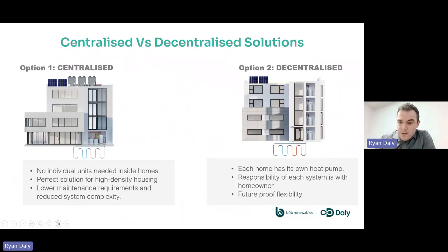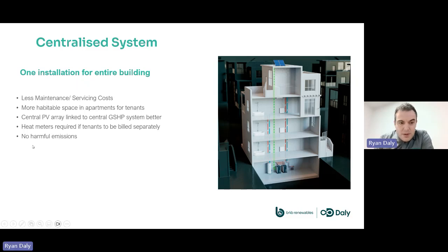And then looking at that a bit closer, the centralized system shows it here a wee bit better. You have two heat pumps in a plant room, buffer tanks and a hot water cylinder. You can have a larger hot water cylinder in the plant room distributing water to all the flats or apartments, or you can also put a smaller hot water tank into each apartment. So just to go through the benefits: less maintenance and servicing costs, you've only one particular plant that you're maintaining, and more habitable space in apartments for tenants.